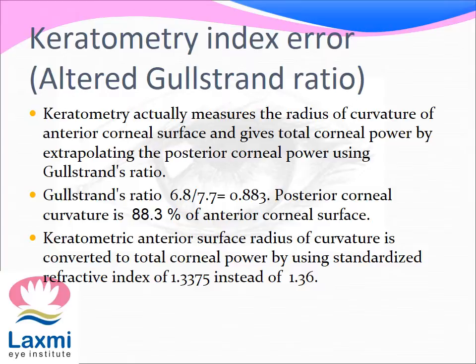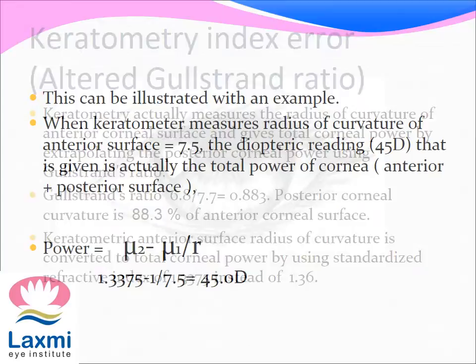Keratometry actually measures the radius of curvature of the anterior corneal surface and gives total corneal power by extrapolating the posterior corneal power using Gullstrand's ratio. If the posterior corneal surface is 6.8 mm and the anterior corneal curvature is 7.7 mm, then Gullstrand's ratio is 0.883 — meaning the posterior corneal curvature is 88.3% of the anterior corneal surface. The keratometric anterior surface radius of curvature is converted to total corneal power using a standardized refractive index of 1.3375 instead of 1.36.